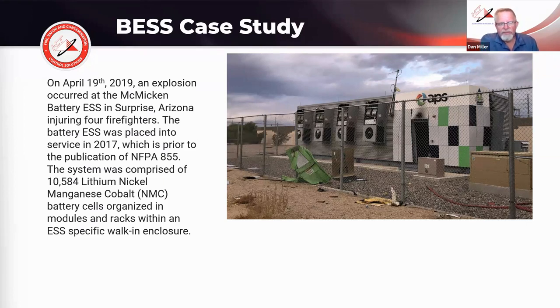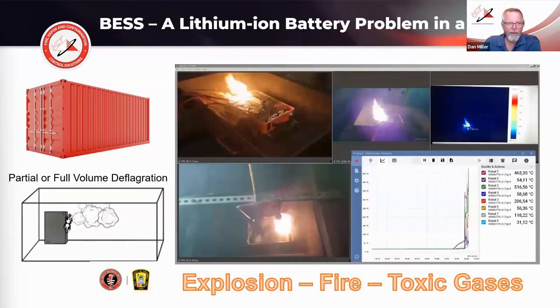The system was comprised of 10,584 lithium nickel manganese cobalt (NMC) battery cells organized in modules and racks inside that specific walk-in enclosure. One of the big hazards is that you have a container in which batteries start to off-gas, and then you can have a partial or full volume deflagration.